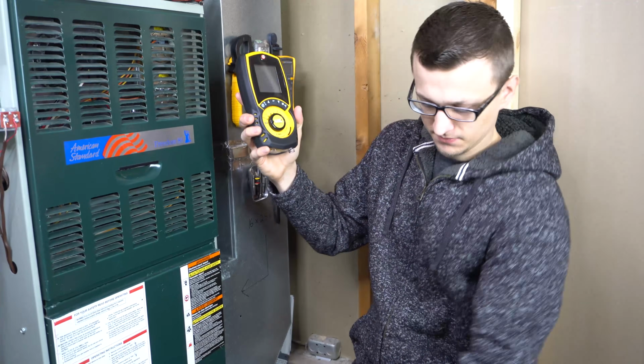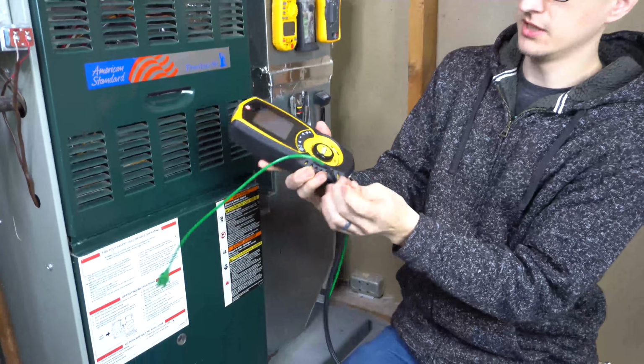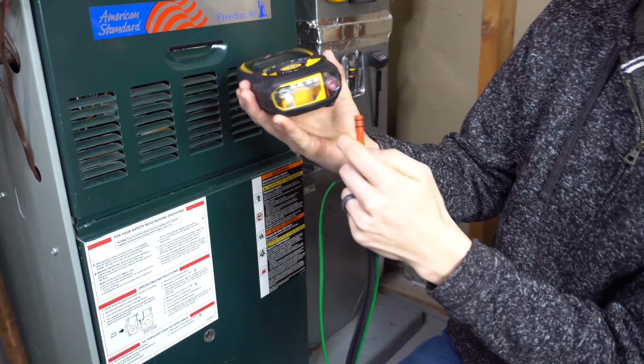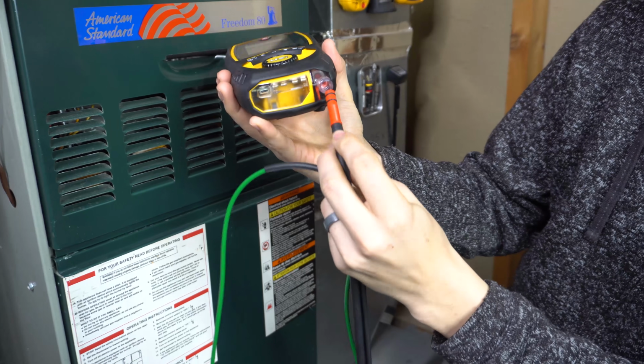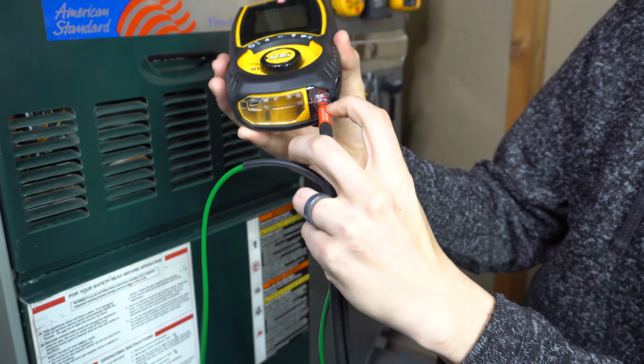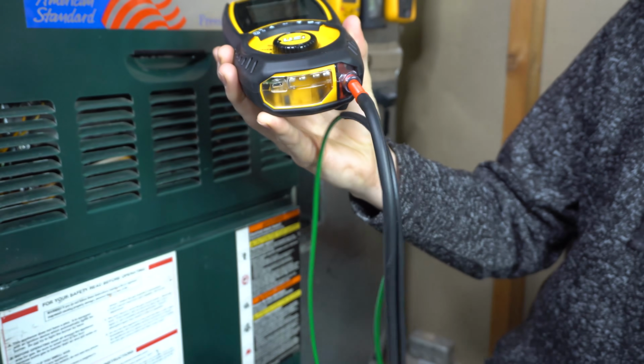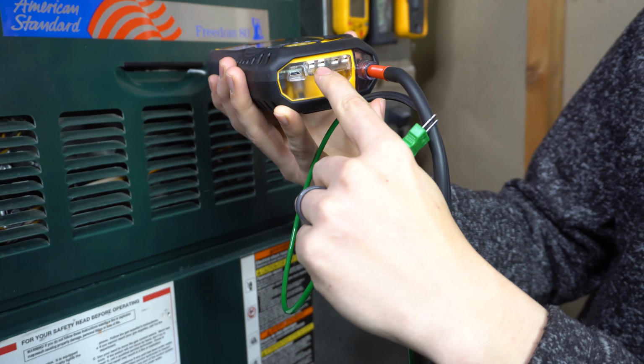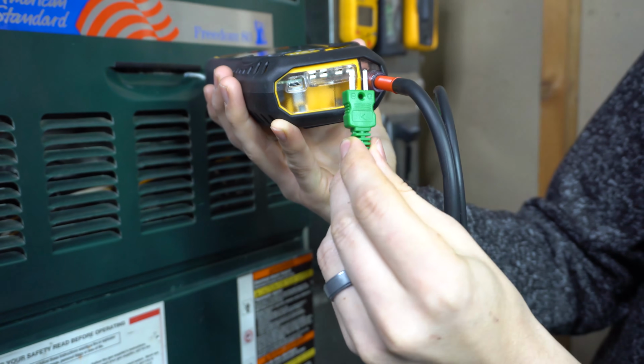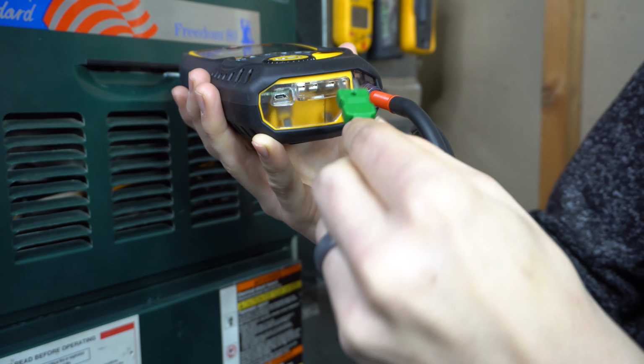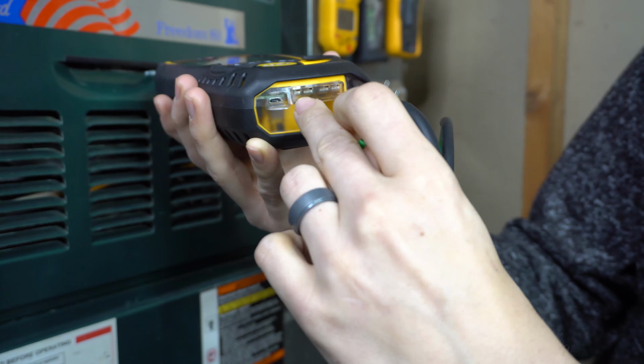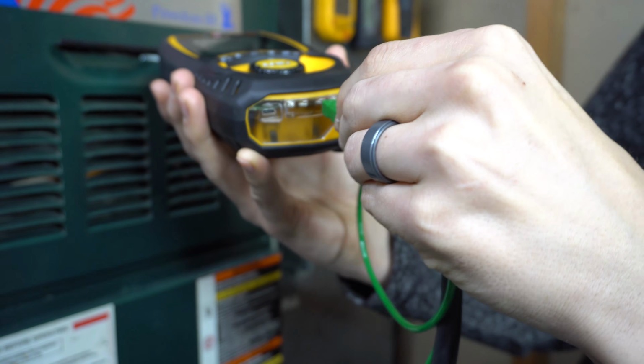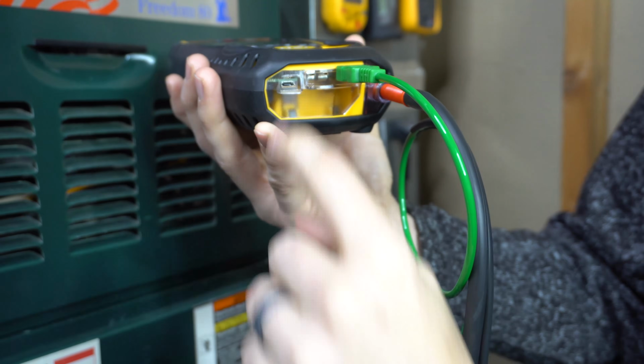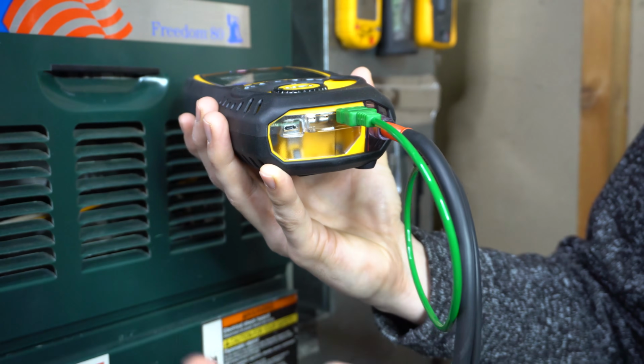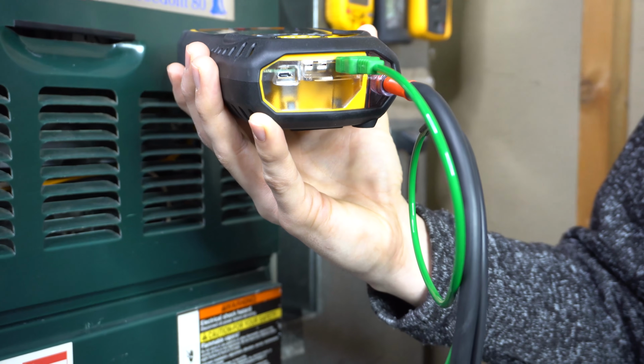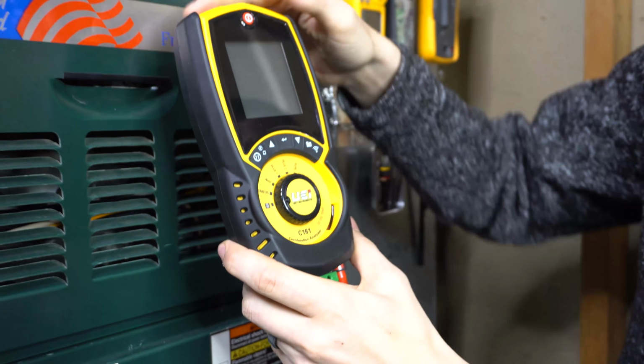I'm going to go ahead and plug in my test probe into the analyzer, and just so you see what I'm doing, here's the port for it. You plug in the tube here. It has the little rubber gaskets to prevent any leakage. And then you have two K-style ports where you put your temperature adapter into. I'm only going to be using one, but later in the video I'll show you why there's two of them. And then there's also a micro USB port right there because this analyzer does have rechargeable batteries. So let's fire this analyzer up.